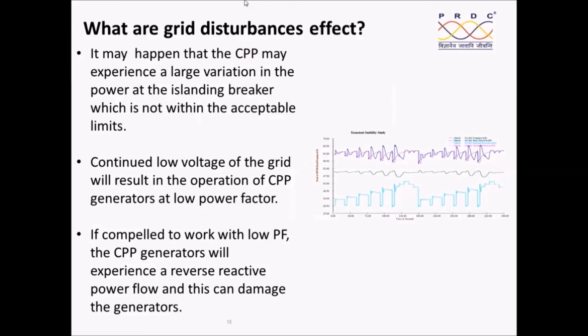What are the effects of grid disturbances? The CPP may experience a large variation in the power at the islanding breaker, or it may see a continued low voltage of the grid, which will result in the operation of the CPP generators at low power factor. If the voltage is very low, the machine may start absorbing reactive power, and then the loss of excitation type of relay may operate because it is going to reverse the reactive power and it can damage the generators. It may try to draw very large reactive power. Therefore, these are the problems associated whenever we don't get islanded.